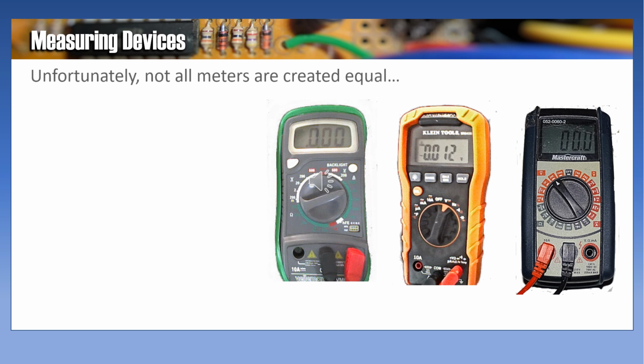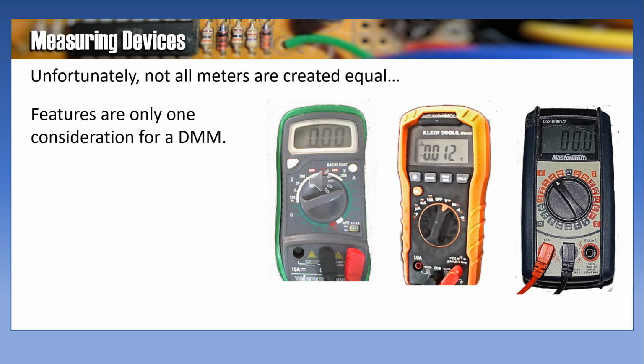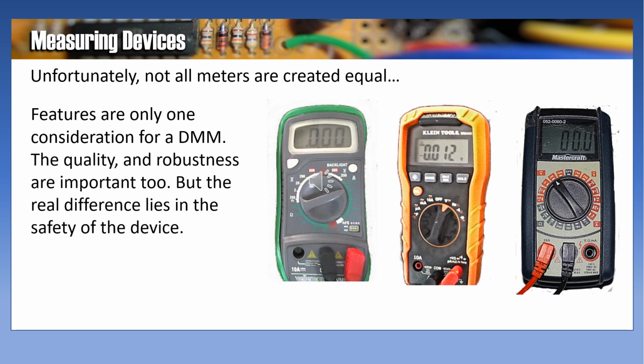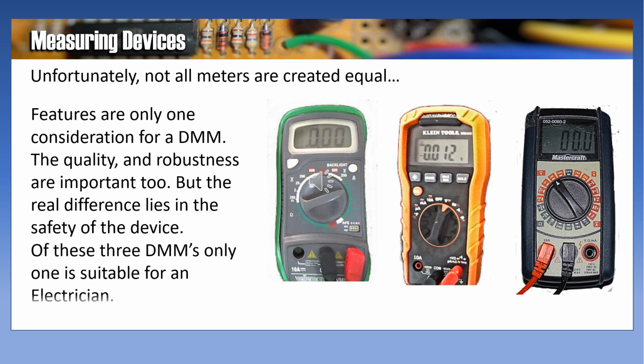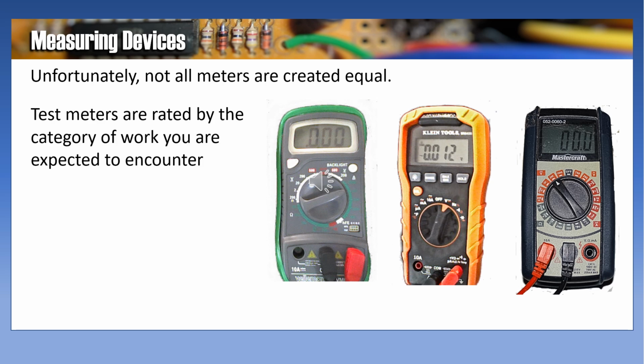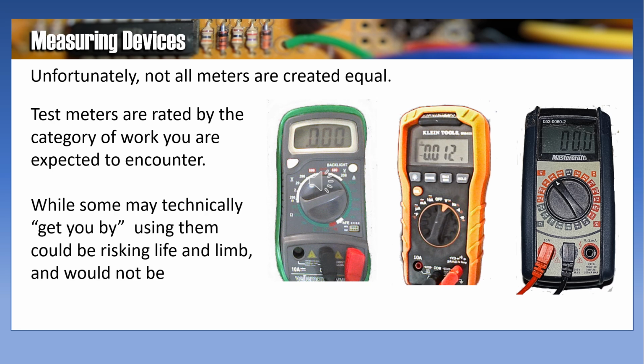Unfortunately, not all meters are created equal. Features are only one consideration of a digital multimeter. The quality and robustness are important too. But the real difference lies in the safety of the device. Of these three digital multimeters, only one is suitable for an electrician. Test meters are rated by the category of work you're expected to encounter. While some may technically get you by, using them could be risking life and limb and would not be following the Occupational Health and Safety Act.